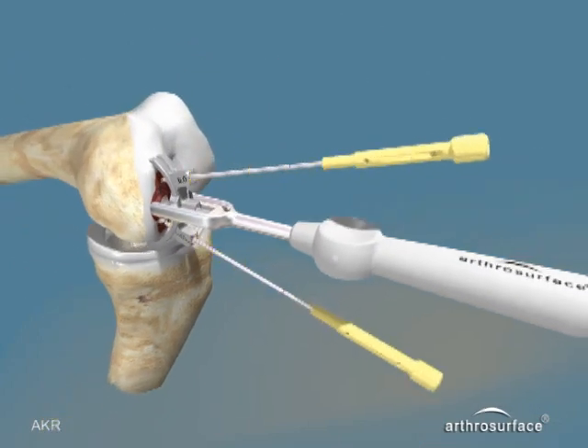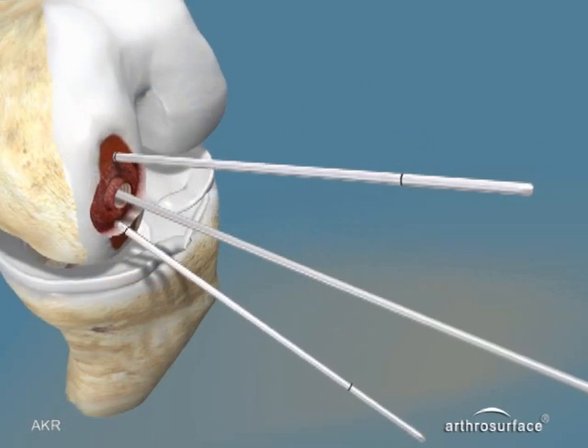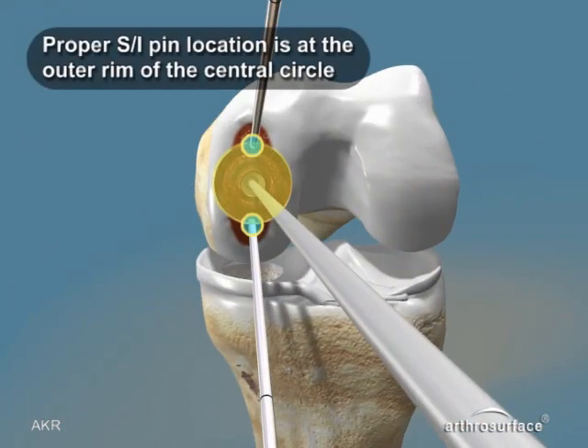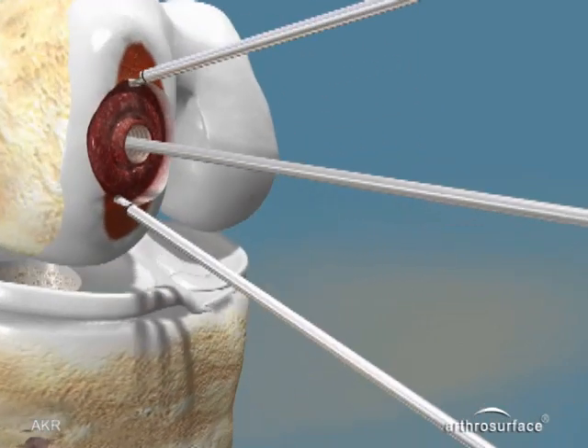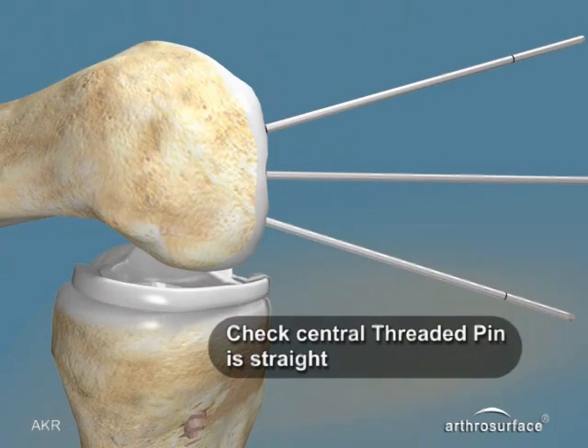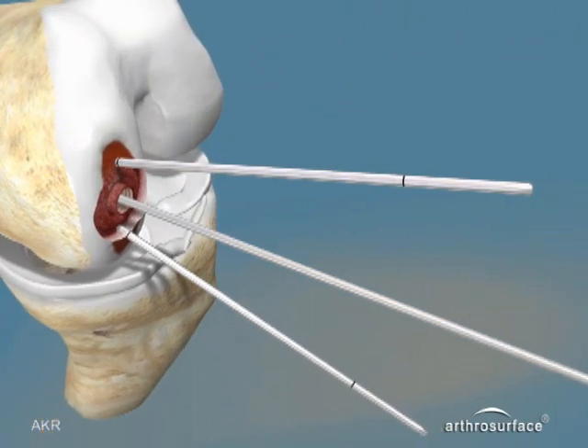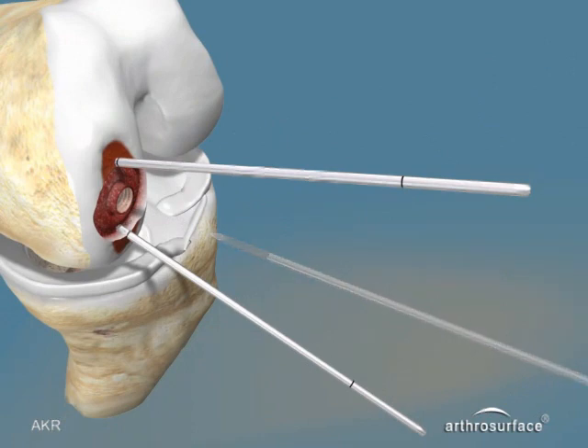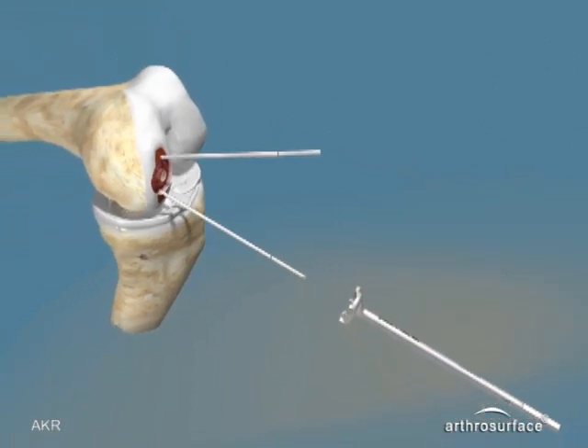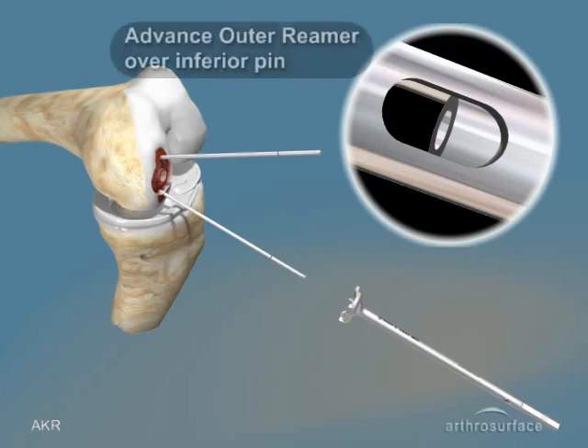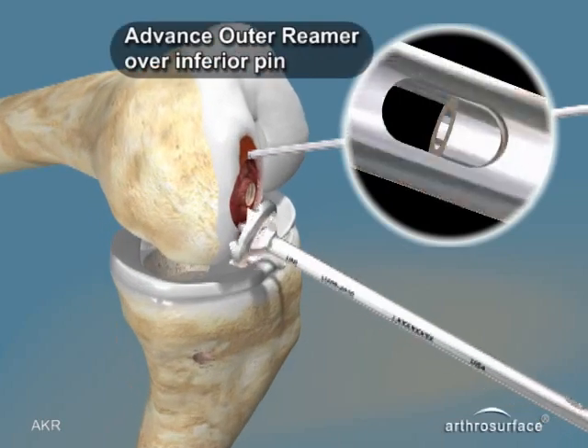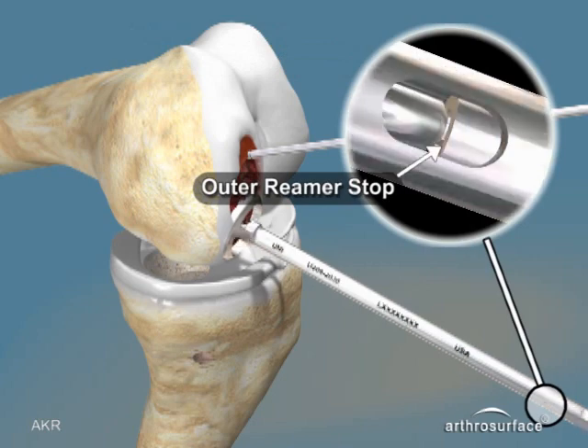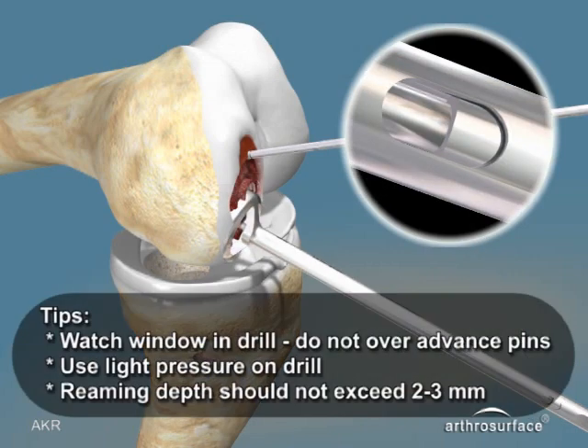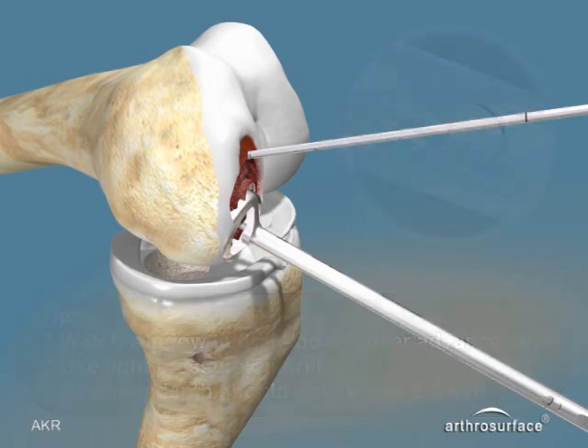Remove the pin sleeves and the femoral guide. Proper pin location is when the small threaded pins are at or within a millimeter outside of the central reamed circle. When satisfied with the placement, remove the central pin. Select the reamer based on the medial to lateral mapping point and ream down until the guide pin is caught into the window. The depth of cut here is approximately 2 to 3 millimeters, and repeat for the anterior circle as well.